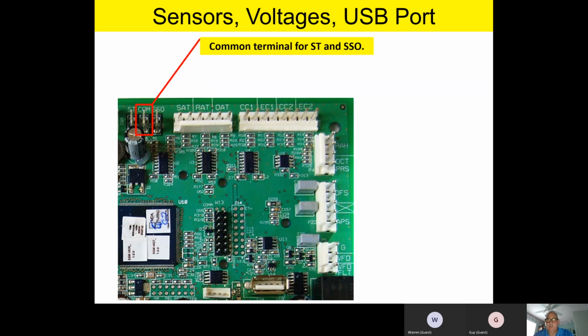Okay, now here's another little cool thing. So let's say, for instance, you've got the space temperature sensor in the space hooked up to ST and common. Now, let's say, hypothetically, it's in a nursing home or someplace, and it's a weekend, and it's an emergency situation, and the thermostat goes bad. Watch this. If you've got a space temperature sensor in the space hooked up to ST and common, even though you're running off a thermostat, if that thermostat should fail, you can go down to the user display and set it up on the board itself and tell the board the types of temperatures you want to maintain in the space.